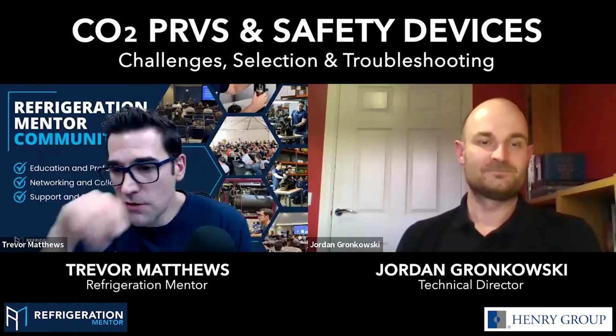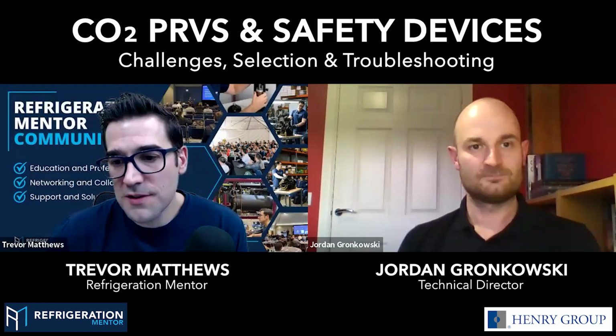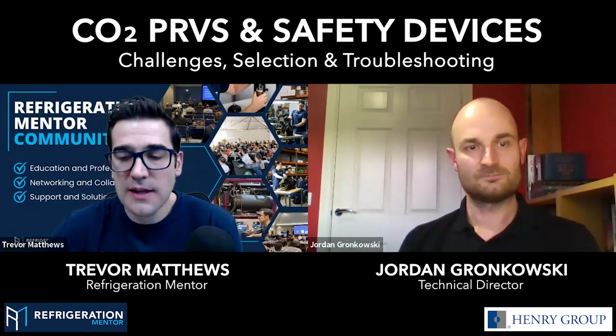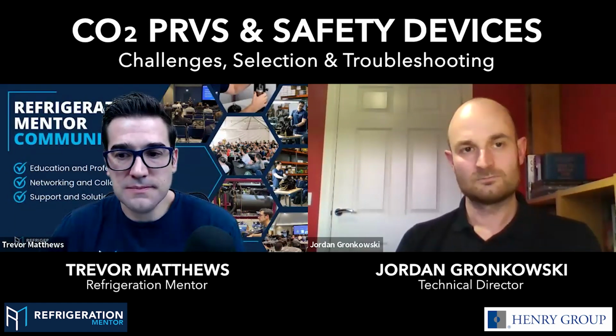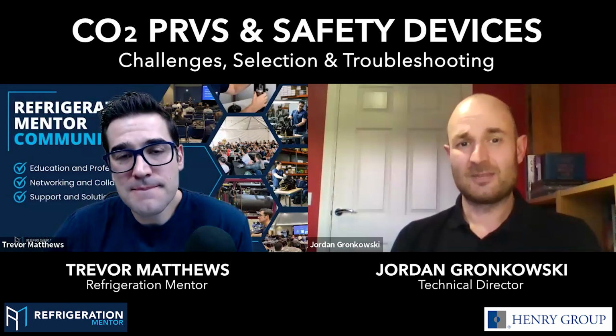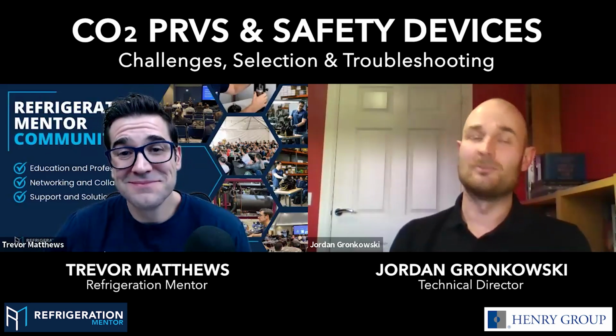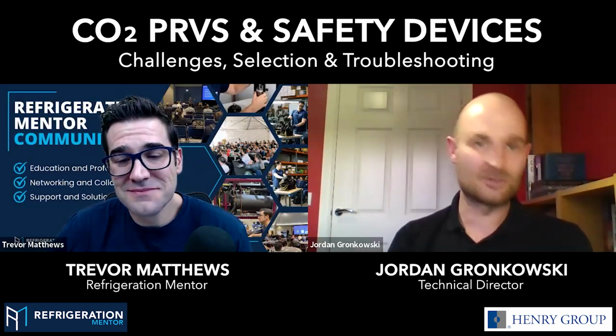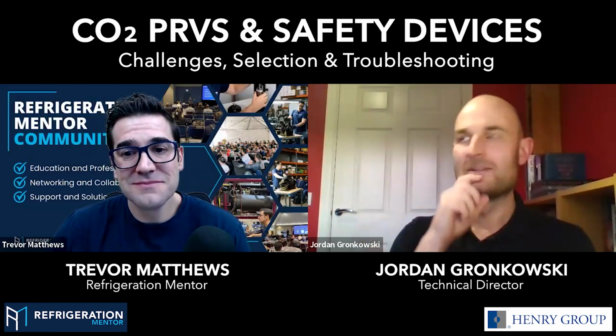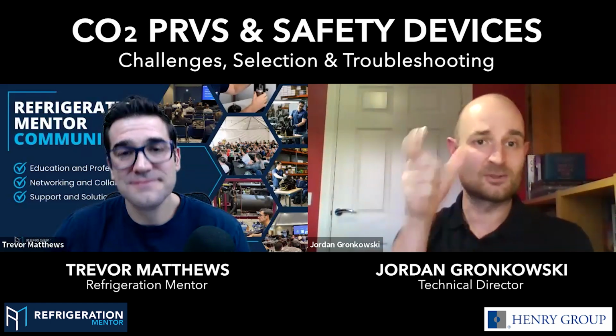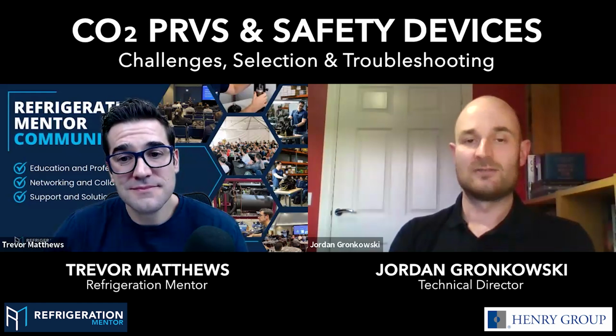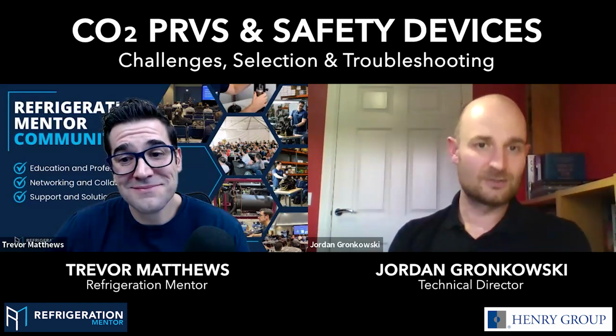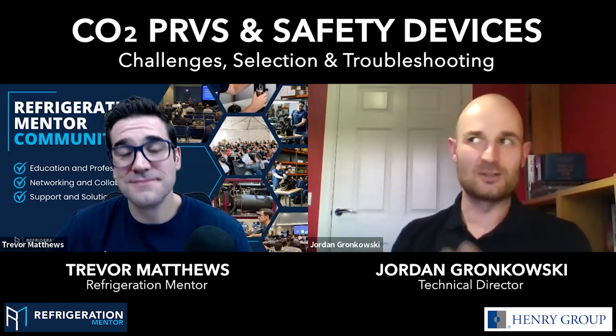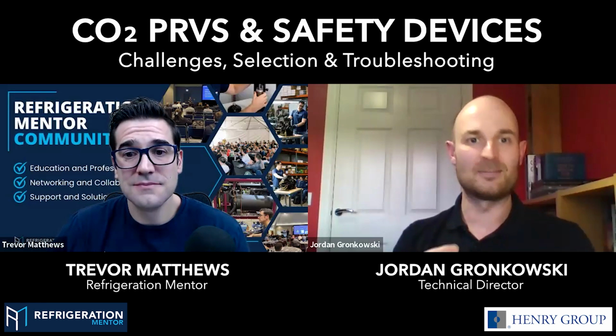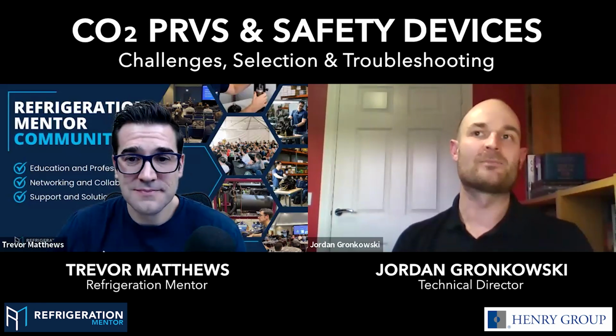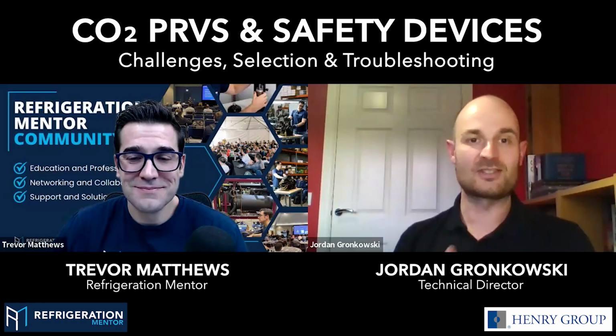Yeah, I've got another good question here. Is there a torque spec for installing a PRV onto a system? It will depend on the thread. That's another good question, something we get asked a lot. Most of our valves, 99% apart from a few specials, are NPT threads, so tapered thread connections. There is no recommended torque for NPT because torque is not a good measure of how well an NPT connection is engaged. So no would be the simple answer.